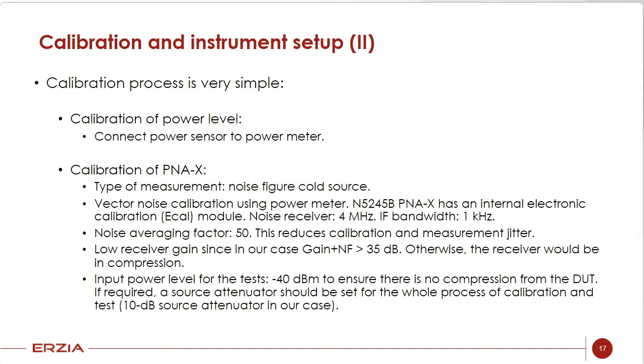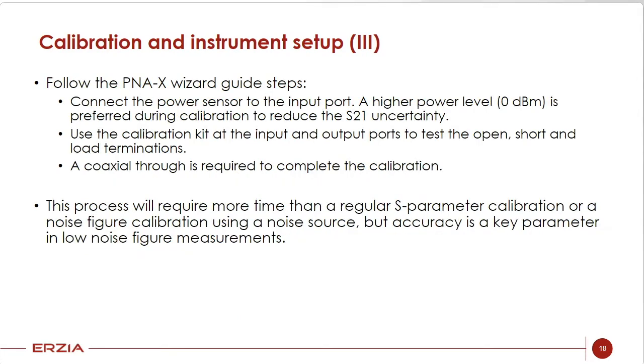Finally, we have set the input power level to -40 dBm to ensure there is no compression from the DUT. If it is required, a source attenuator must be set for the whole process of calibration and test. It is very important not to change it between the first step of calibration and the test step. In our case, we have used a 10 dB source attenuator. Then we just follow the PNA-X wizard guide steps.